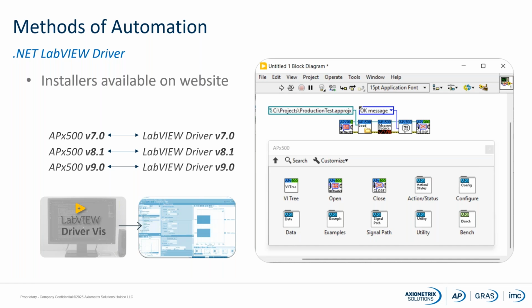We do also have a LabVIEW driver. So if you like to work in LabVIEW, you can do so with APx. But just a couple things to know if you plan to use the driver are that A, the driver version that you download and install from our website needs to match the APx software version that you're running. And then B, it is software control. It's not a VISA driver or anything like that.